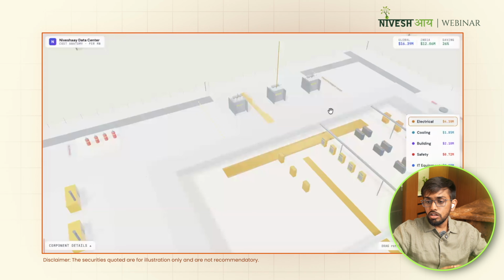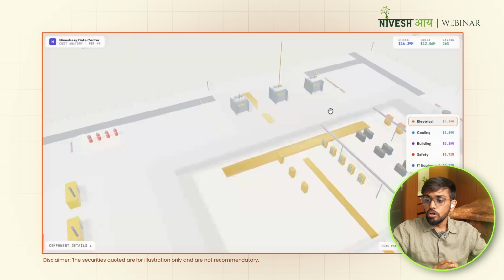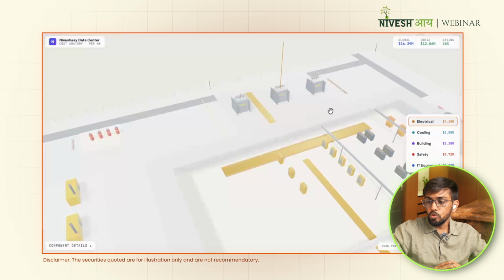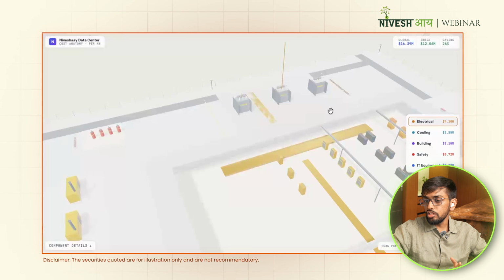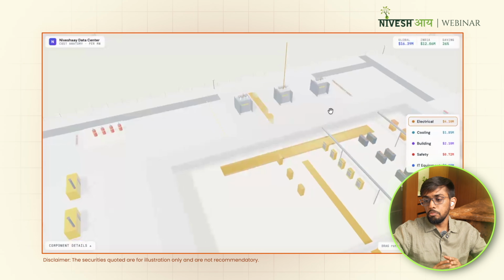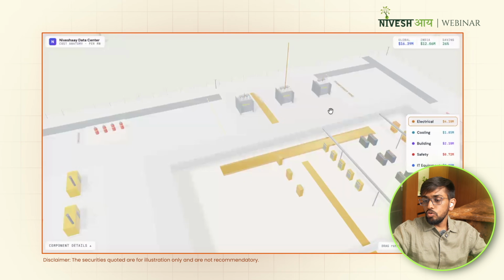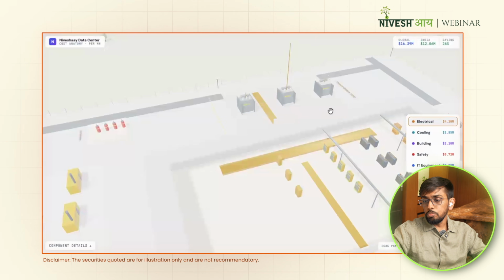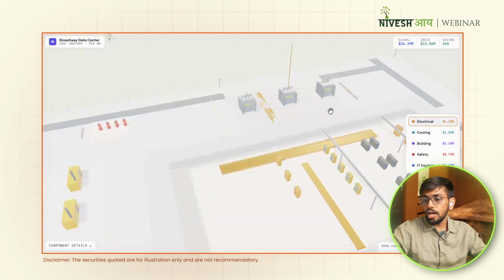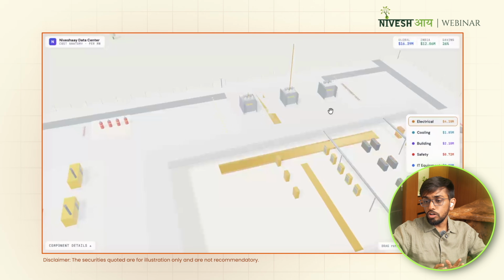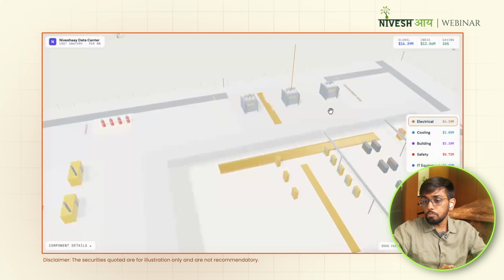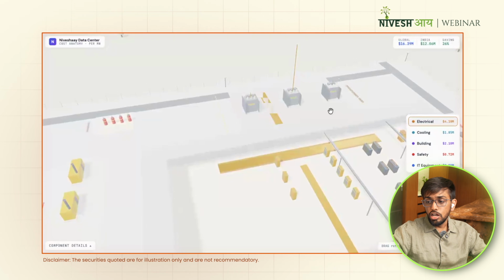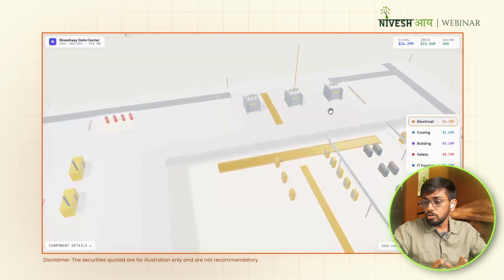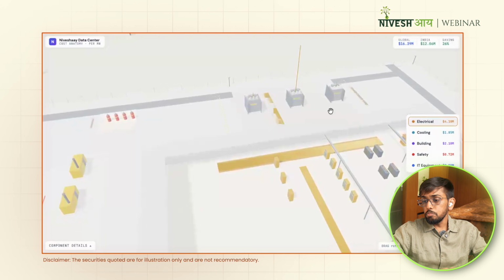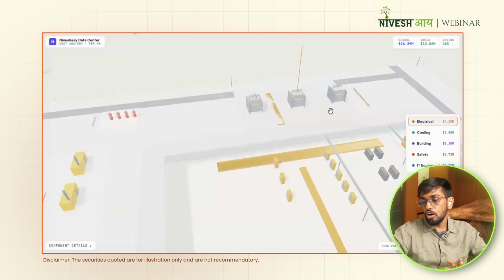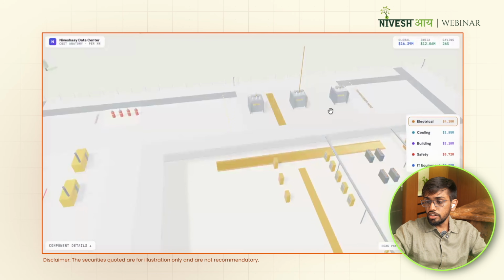To quantify this further, 1 gigawatt of data center capacity being put down by these hyperscalers or enterprise players will, depending on its type, roughly cost 10 to 15 billion dollars. In rupee terms, that's 1 lakh to 1.5 lakh crore per gigawatt. Globally, we're talking about 100 gigawatts of capacity addition coming in the next few years. Electrical, in that 1 gigawatt of capex, is almost 20 to 25% of the capex, which includes transformers, gensets, UPS and other grid interconnection infrastructure.